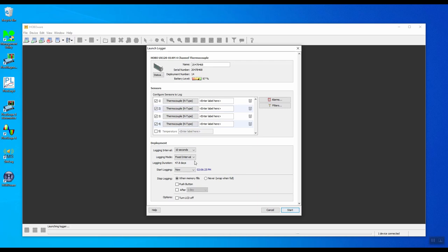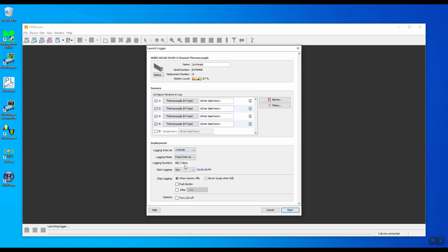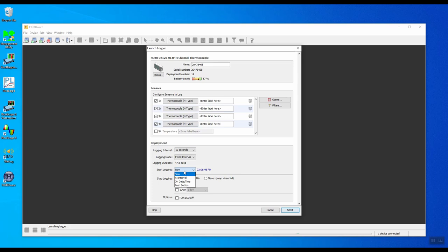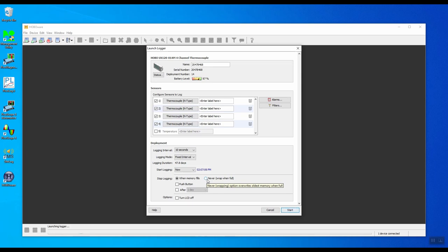The logging mode will leave it as fixed interval. The logging duration is 47.8 days because we've used 10-second sampling and four channels. If we changed it to one minute, the number of days increases to 286 days. This indicates when you want the logger to start recording. We'll leave it as now. The next section says what you want to do when the memory fills up. We'll have it continue recording, so it will overwrite the oldest data. That's wrap when full. Then click on the start button.